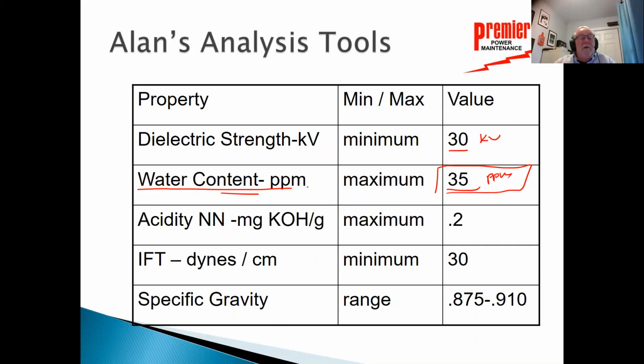We need to also take the temperature of the oil when we take the sample, so we can actually look at this water content. If the oil is warm, it can hold a lot of water. It'll suck it in, and we can see that there. If the oil is cold, it can't hold the water or the moisture. So the moisture will either be in the paper or in the bottom of the tank.